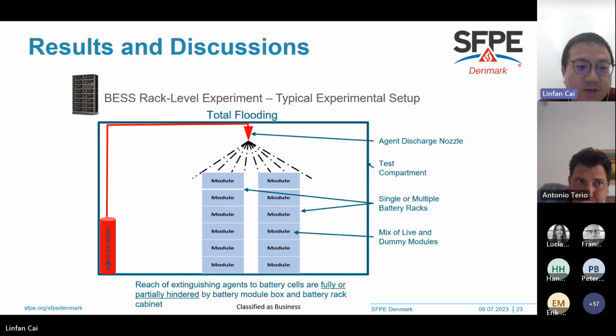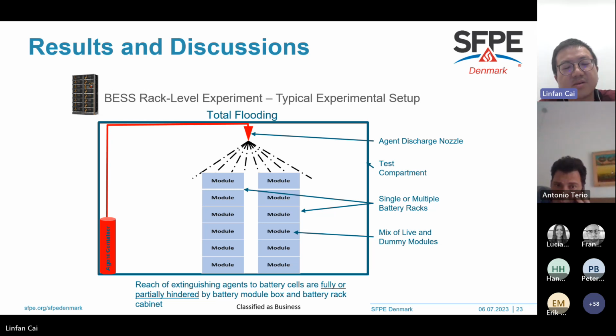Coming to the battery energy storage rack level experiment: this is the typical setup, where all battery modules are housed within a battery rack. In the experiment, single or multiple battery racks are normally located in an ISO standard container, with extinguishing agents applied on top of the racks. If a battery module on a lower tier catches fire, the extinguishing agents may or may not be able to reach it since it's blocked by other modules, which could be one of the main problems at the rack level.